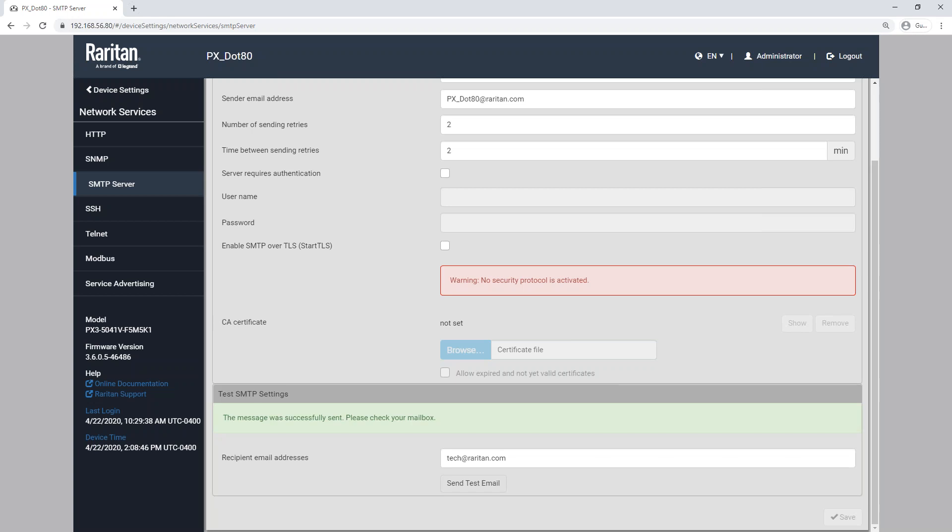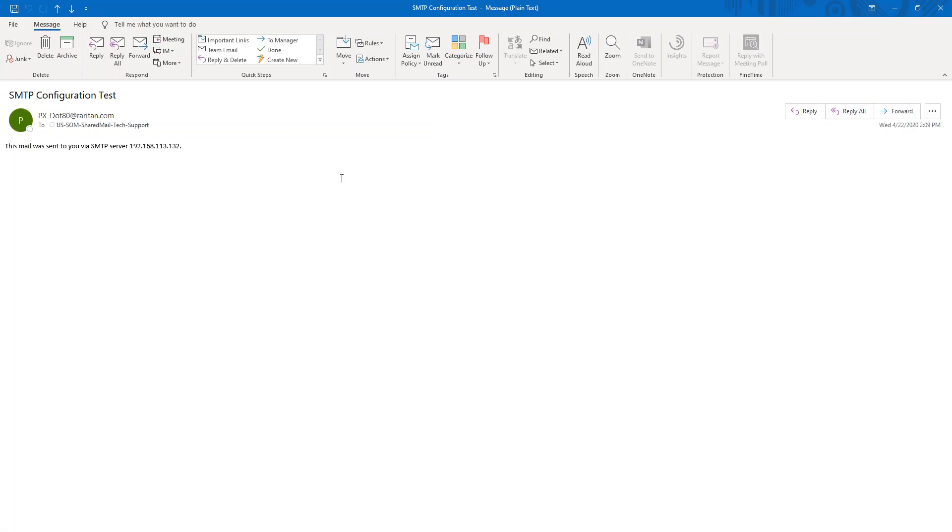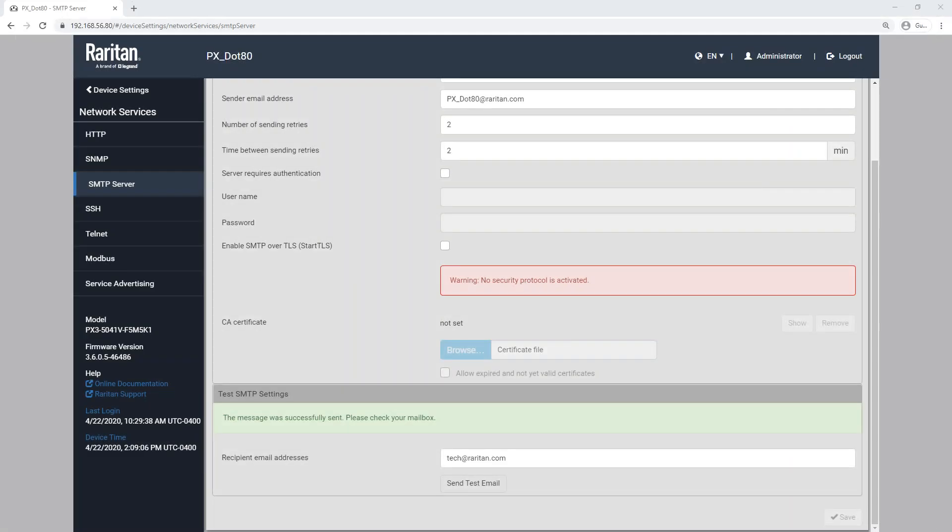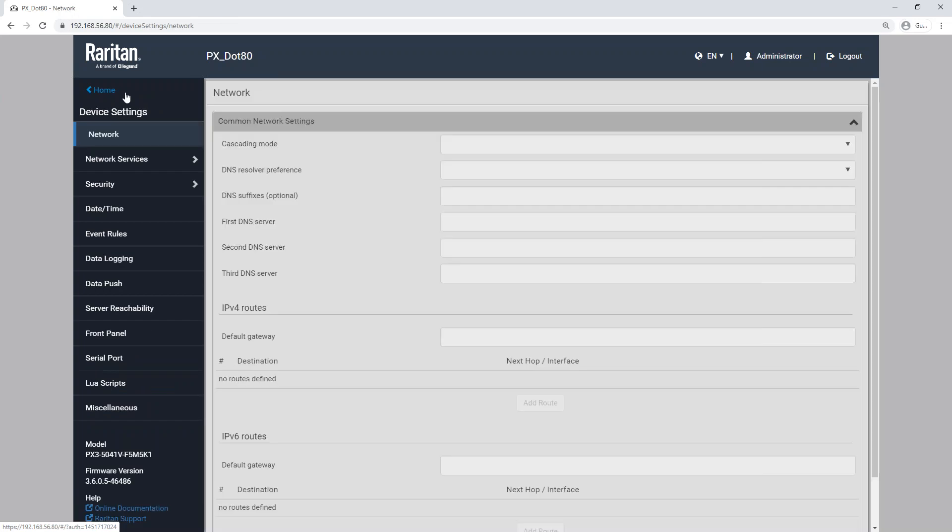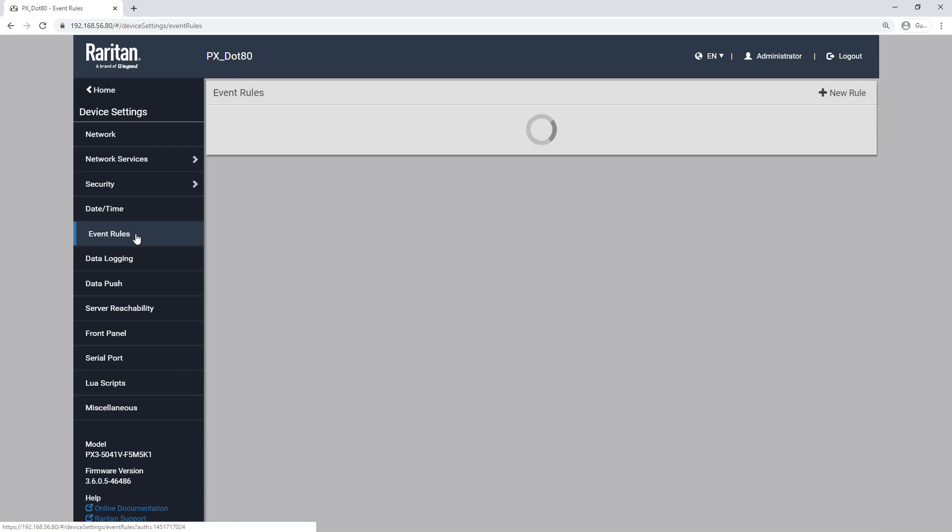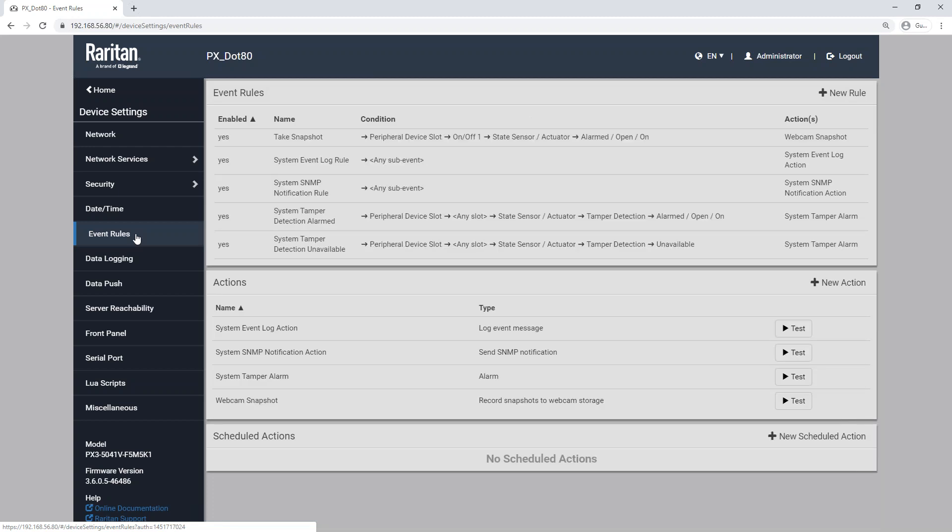All right, there we are. So this is what the email test looks like. So just SMTP configuration test came from PX_Dot80 at raritan.com, and it tells me the server that it was sent from. Now, the other key portion to getting email alerts is we actually have to set up an event rule to do that. So we've configured the SMTP server. We're going to go back into event rules. So I showed you what the SNMP event rule looks like, and that's automatically generated on the PDU. The email is not. So we have to create that.